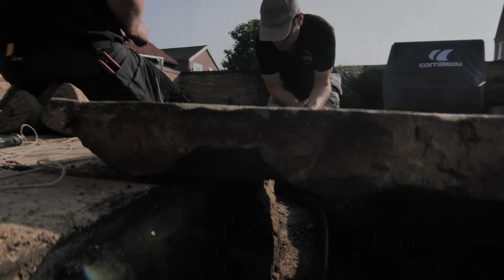So rather than putting in a 6mm or 10mm armoured cable just to supply the Zappi, we decided to spend a little more and put in a larger 16mm 3-core cable that gives the building plenty of capacity. Doing that means this trench doesn't have to be dug again.